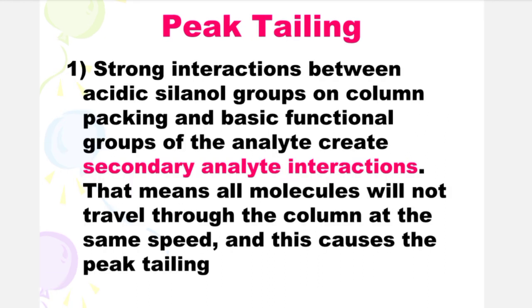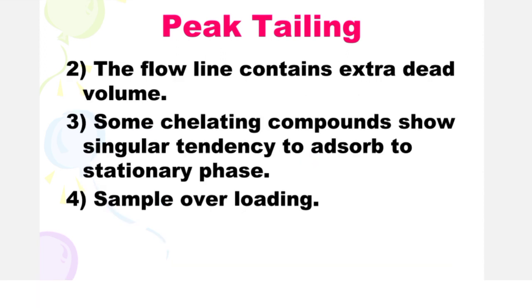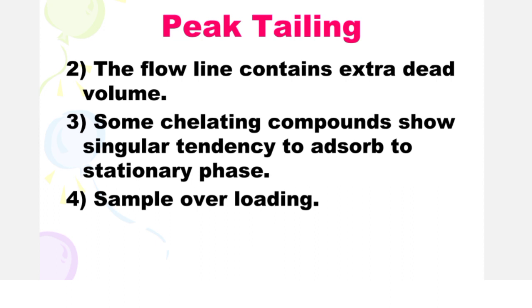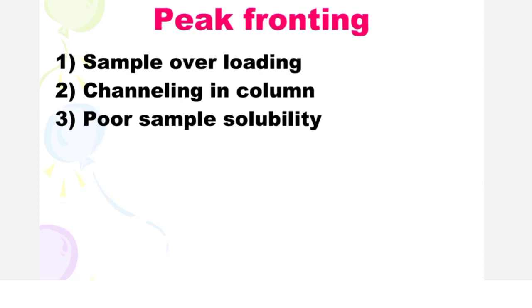Next is peak tailing. Peak tailing is due to strong interaction between acidic silanol groups on column packing and basic functional groups of the analyte, creating secondary analyte interaction. That means all molecules will not travel through the column at the same speed, and this causes the peak tailing. Peak tailing is also due to when the flow line contains extra dead volume.